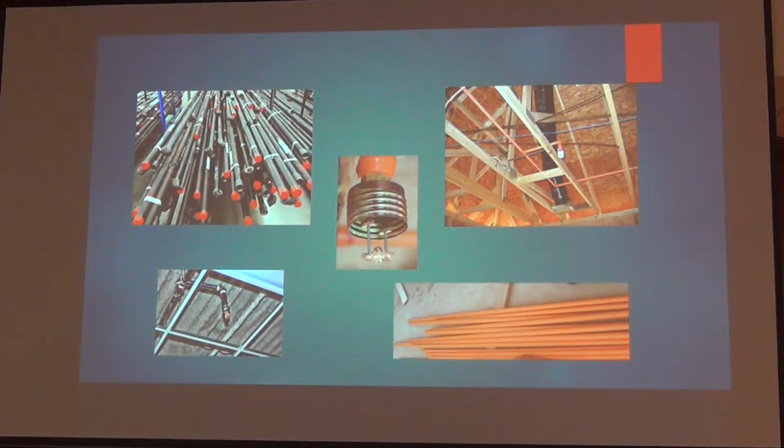You can have a mixed system, but that floor ceiling assembly is also rated for 2 hours. But you can go 4 floors above. You can go 4 floors above still, yes. But then it's required to be a 13 system after that. New code change, 21.